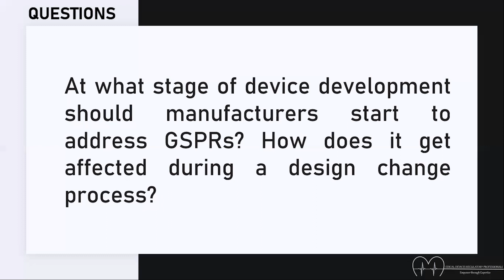Right. And I think at every point, we have to remember that manufacturers are performing risk analysis throughout their design process. So, like you said, from the time you start your design inputs, that's when you're going to start thinking about how it's going to translate in terms of the risks that are posed by this device. So from that stage itself, you're going to start thinking about GSPRs and start building the checklist and start writing how exactly your device is functioning, how it is mitigating the risk, and how it's going to conform finally to the associated GSPR.